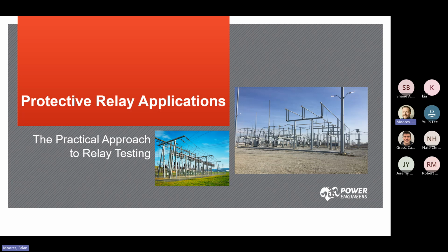Appreciate it. We'll continue the conversation around protective relay applications and really the approach to testing. We talk a lot about the power system, transmission system, all the elements of the system, the protection and the controls and the relaying, at a high level, conceptual level, fundamental level, application level, but there's another layer, and all of this stuff has to be designed, engineered, built, tested, and commissioned. And testing and commissioning is one of the most important phases, if not the most important phase, because you have to get it right. There's no 95% out of 100. The testing has to be right. And the test personnel need to understand the design intent to be able to capture and identify any issues or any misapplications or design errors.